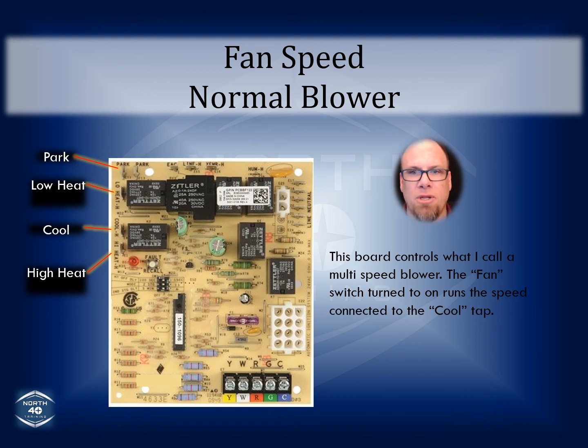One thing that you'll find out, once you start actually checking your blower speeds, is that your high heat and your cool speed will usually be very close to the same speed, and oftentimes will be the same speed. It's not the traditional way we used to do things. Traditionally, high was always cooling, low was always heating. Now they're pretty close to the same in most applications, and that's because nowadays we're doing load calculations, and the load calculations are very precise on BTUs for loss and gain on both heating and cooling side, and so it's an interesting thing once you get to starting checking these things.